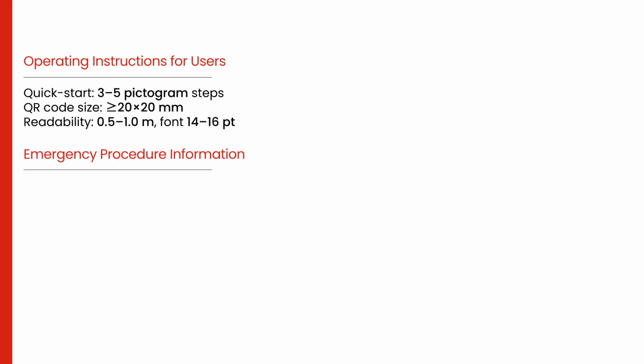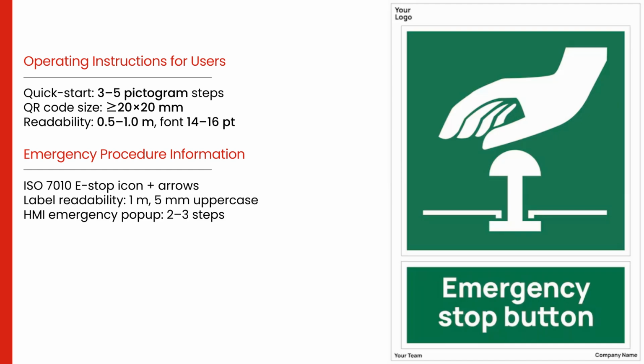Emergency procedure info must be unmistakable. All e-stops should have ISO 7010 emergency stop icons with directional arrows and red markings. Labels must be readable from 1 meter, following the 5 mm uppercase rule, and the HMI should display a 2 to 3 step emergency pop-up.